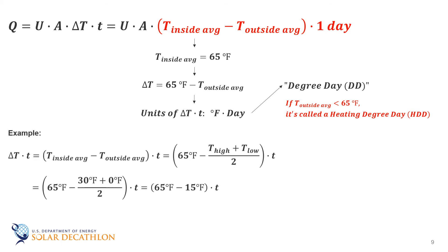As an example, let's say the low for a winter day was zero and the high was 30 degrees Fahrenheit. The average temperature is then 15. Subtract that from 65 and the delta T for the day is 50 degrees Fahrenheit. We refer to this as 50 heating degree days or a 50 degree F day for units. These units are important. Remember that you only tabulate a heating degree day if it is a positive number. If the average temperature for the day is over 65, you ignore that day.